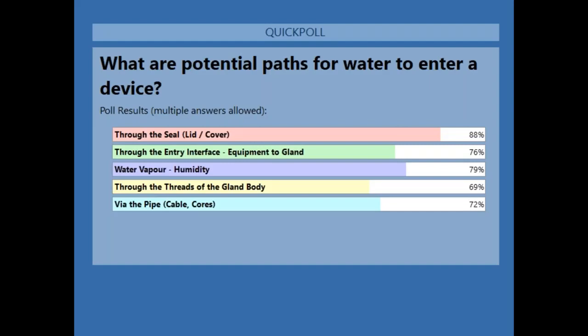Now, what are the paths for potential water ingress? Guys, every single way. Through the cover or the lid, a broken seal, a loose lid. Through the threads of the gland threading into the device. Through water vapor, humidity. IP ratings do not matter when it comes to vapor or gaseous form of water. When humidity gets into a device, when it condenses into water, the water's now inside. IP ratings only stop solids and liquids. Yeah. Through the threads of the gland body. So through the other threads of the gland, not just the entry thread, but the main body and the back nut.